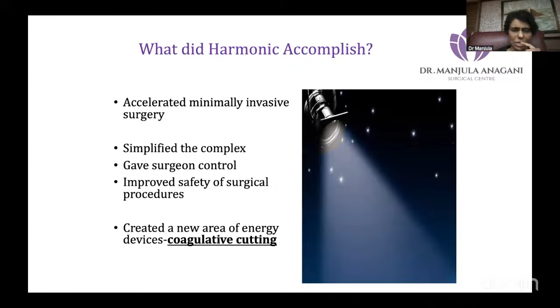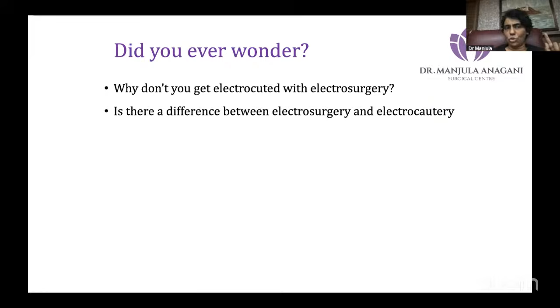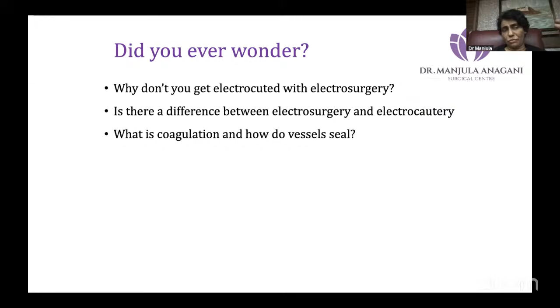So coming back to our questions, why don't we get electrocuted? Because for all the surgical instruments the frequency goes beyond 250 kilohertz. The difference between electrosurgery and cautery: in electrosurgery, which is what we use in our hospitals, the electricity goes through the patient. Coagulation and vessel sealing is always the interlink between compression, temperature, and time. With the pulse technique, we use a few seconds. Temperature does not go beyond 150 if you use the pulse technique. And the compression we do manually.